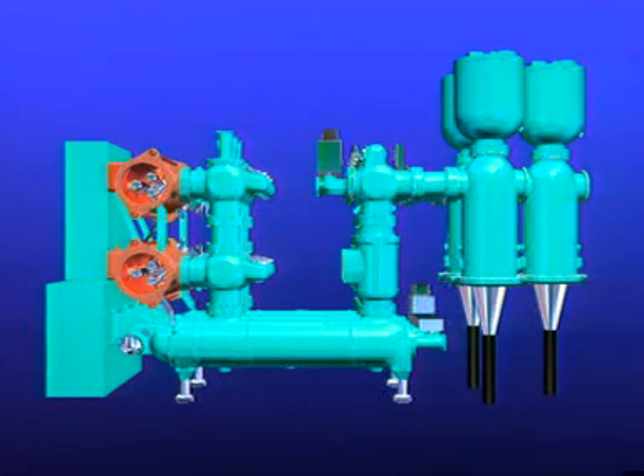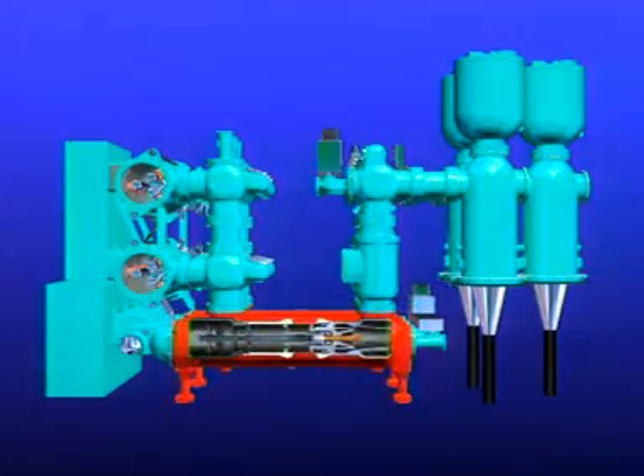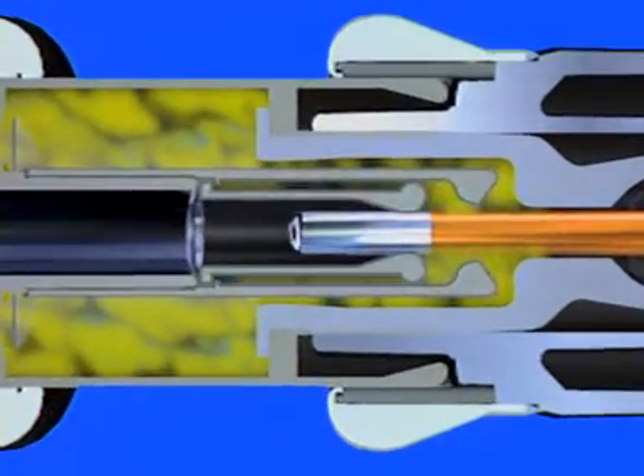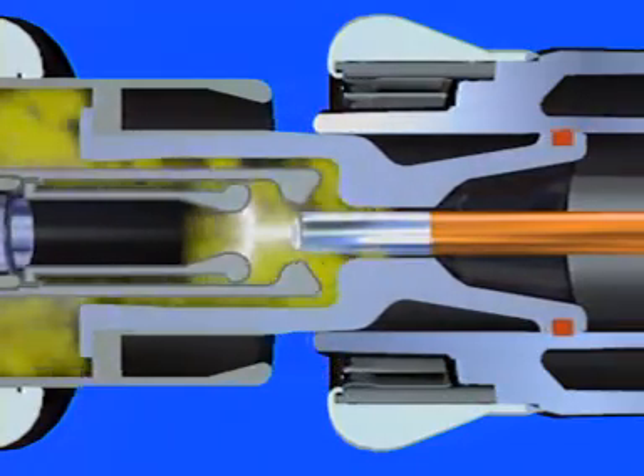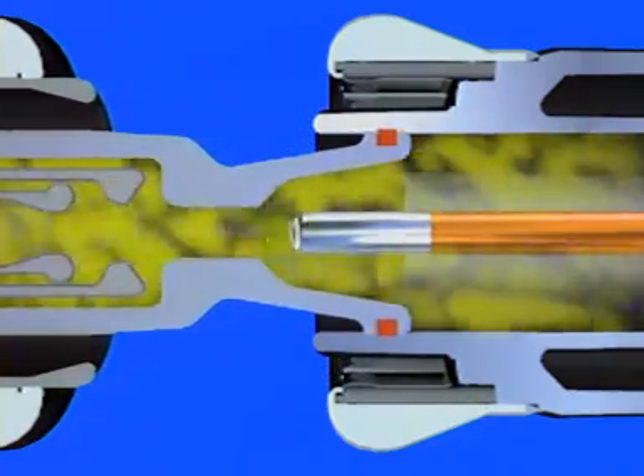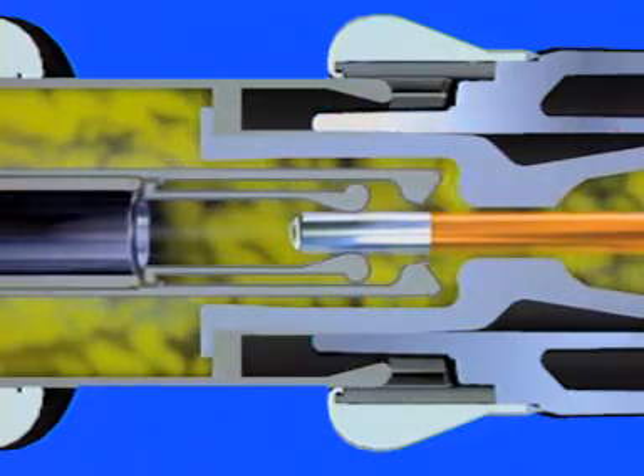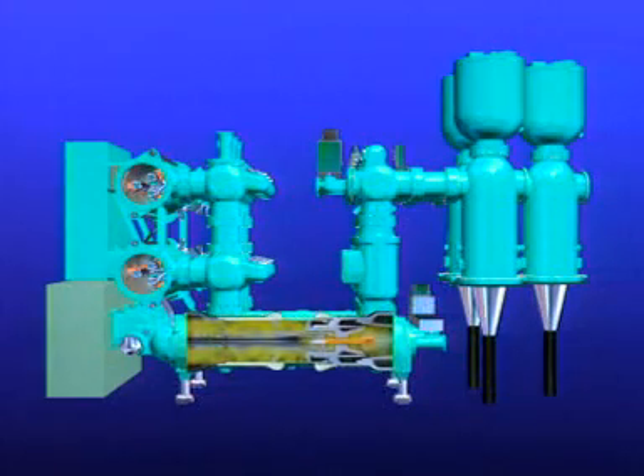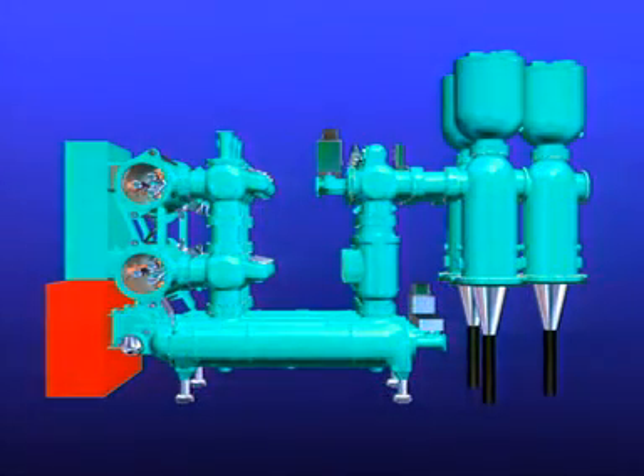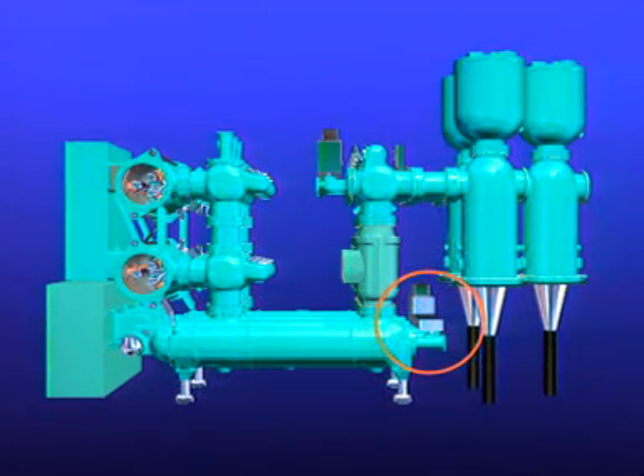Its busbars are also three-phase encapsulated. The busbars linked to the circuit breaker can be interrupted via disconnectors. A pin contact serves as the work-in-progress earthing switch. In this type of GIS, the interrupter units are single-phase encapsulated. They also operate in accordance with the self-compression principle already mentioned. The stored energy spring mechanism supplies the making and breaking energy. At the same time, corner gears transmit the energy to the three interrupter units. A pin contact serves as the work-in-progress earthing switch.